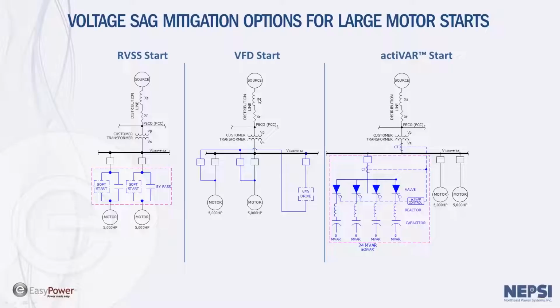In this situation, we show a VFD, sync bus and bypass breakers. So in this case, we have one VFD drive feeding two motors. Essentially, one motor is started, and once it's brought up to speed, the bypass breaker is closed and brought onto the customer bus, and then the second motor can be started. This is very typical for gas pipeline type stations where you have multiple motors that need to be started, and speed control is not required.